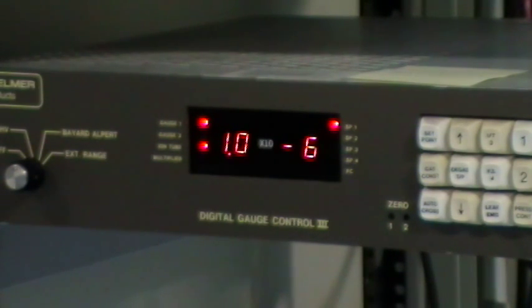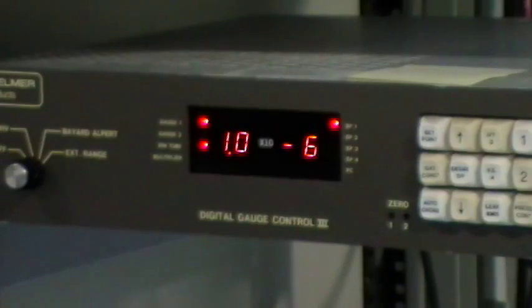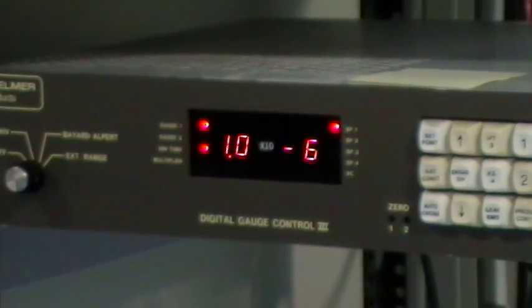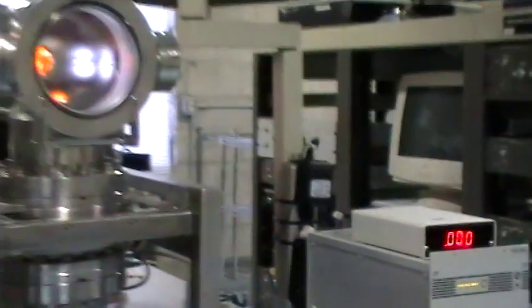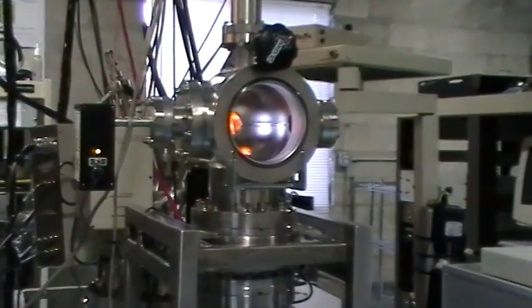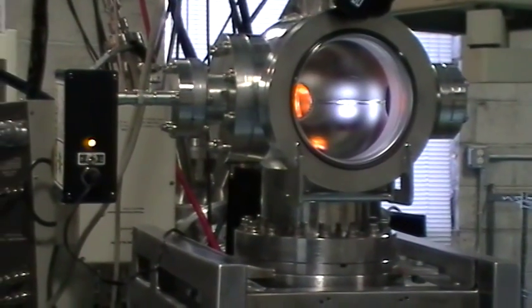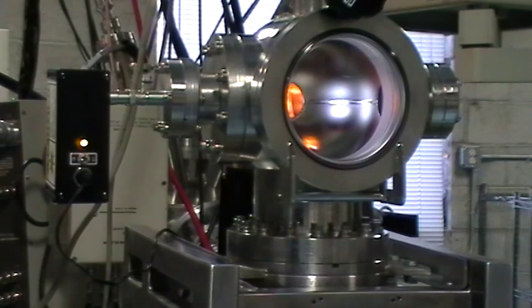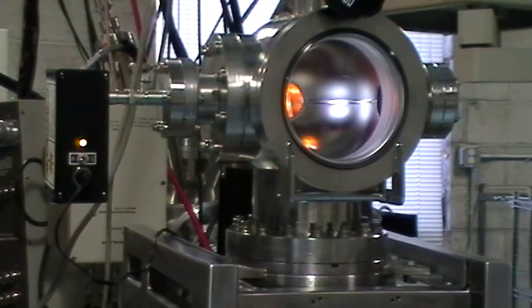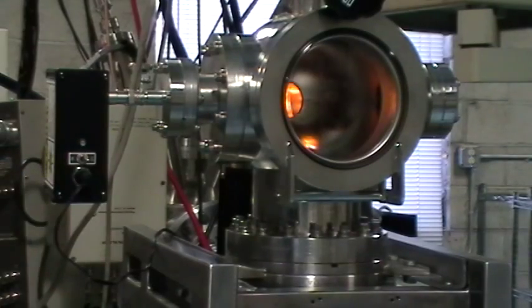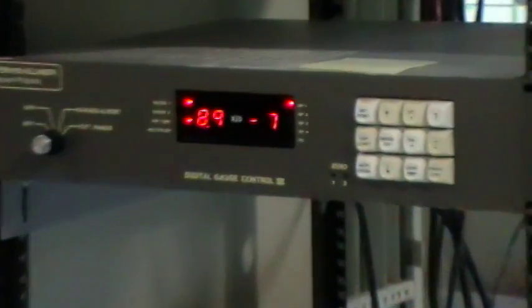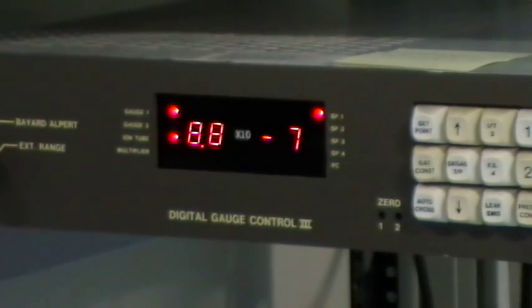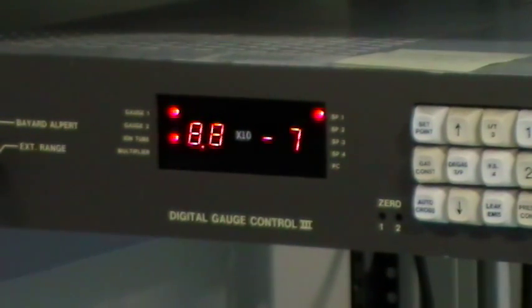And here we're looking at the ion gauge. What we're going to do here is turn the miniZ off and see what the effect is on the ion gauge reading. And we can see that it drops from 1E-6, it comes down into the high 7s and on its way down to the mid 7s fairly quickly.